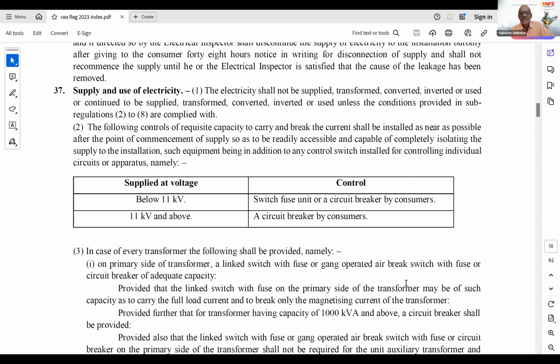There ends the matter. That doesn't mean that if your distance goes beyond 50 meters, 100 meters, or beyond 300 meters, you provide more. So these are all not required, and these are all the discretionary powers of electrical inspectors. It is not a deviation. It is accepting the provision, and you have to apprise the electrical inspectors. In most of the states, a single breaker without any additional breaker near the transformer is being accepted, even for a 1000 kVA transformer. So these are the cases where the discretion can be exercised wrongly.